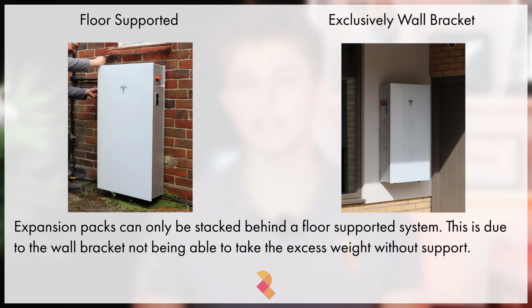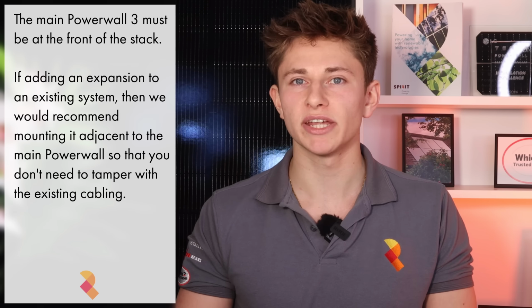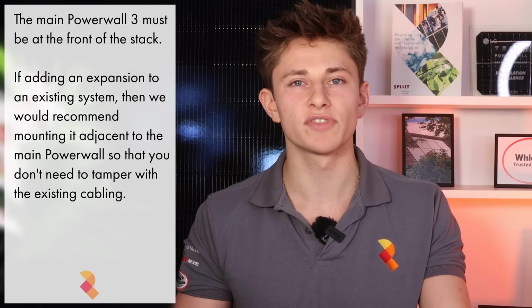If you do want to stack them, then you need to make sure that the whole system is floor supported. You can't install the main Powerwall 3 above ground and then put an expansion pack behind it, as the wall bracket is not strong enough to hold both at once. Something important to note is that the main Powerwall 3 always needs to be at the front of the stack.